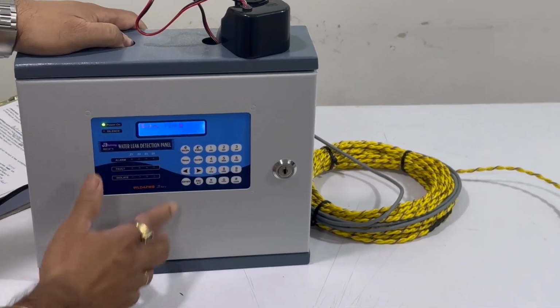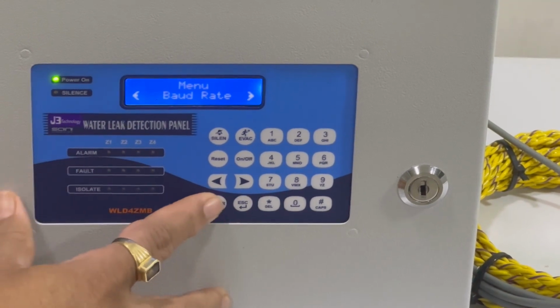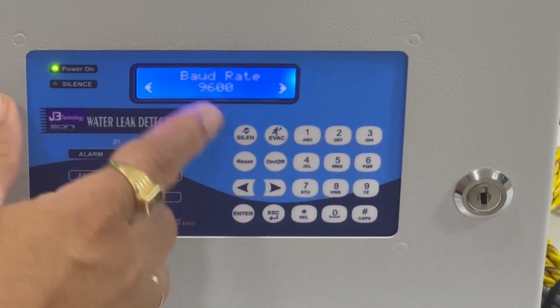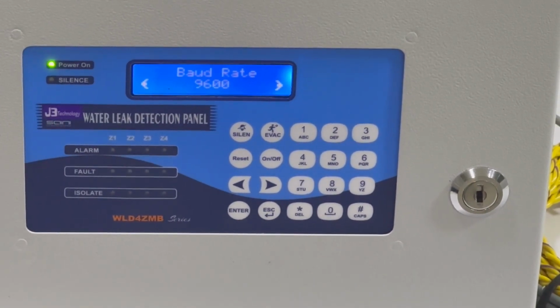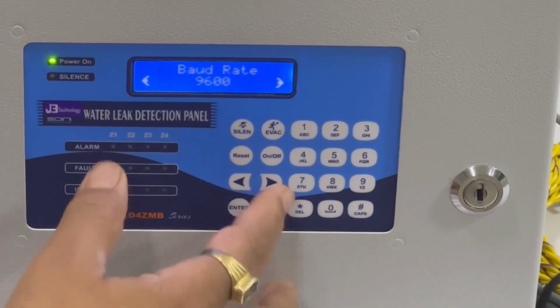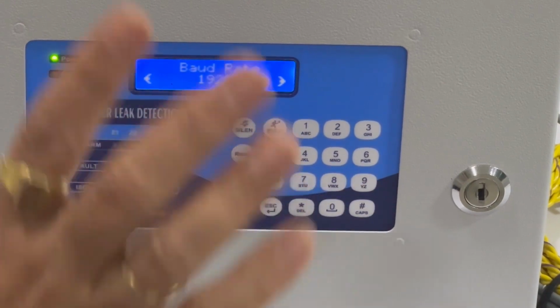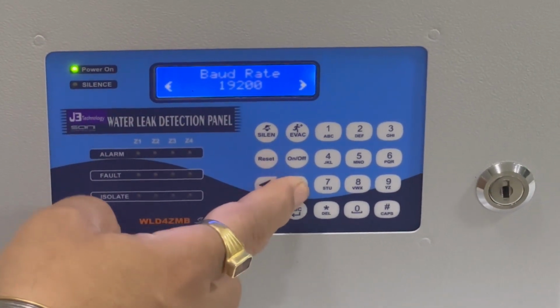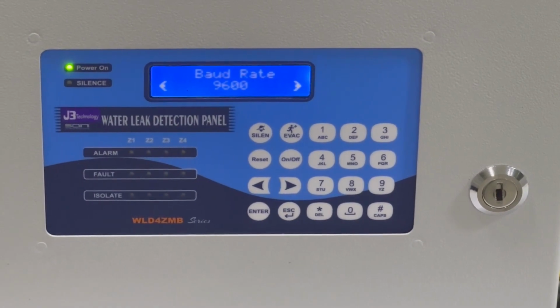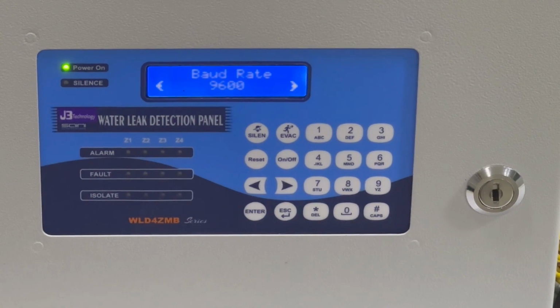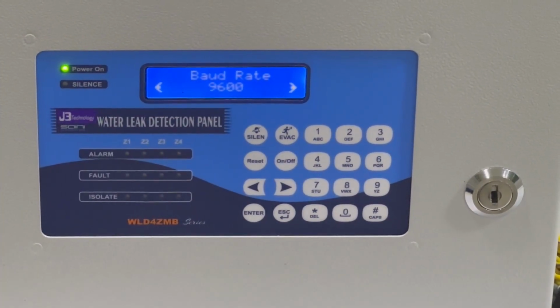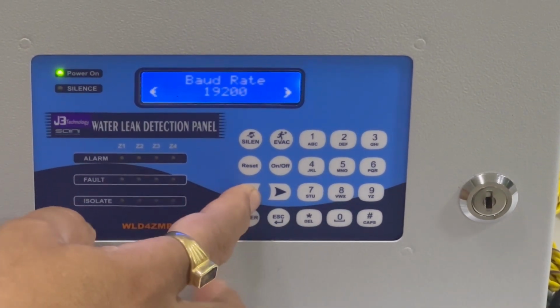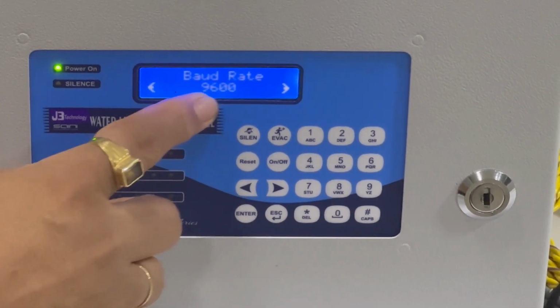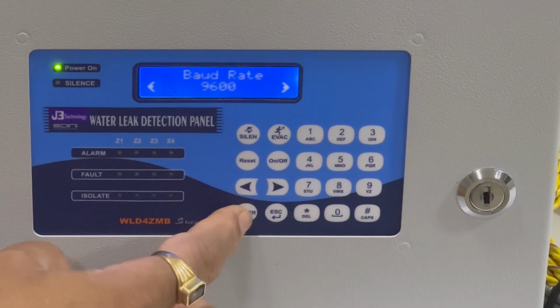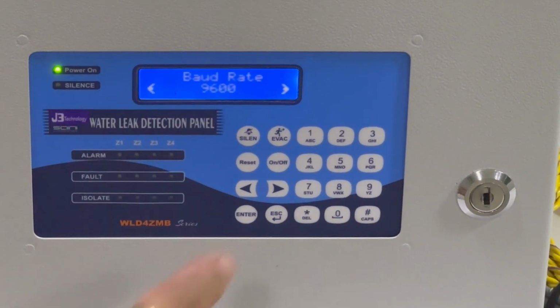Now guys, I will show you the next feature of this panel. The BAUD rate. The BAUD rate is basically used for connecting the BMS. For BMS, you just have to enter. According to your third party service, the BMS, the building management system, may ask for a BAUD rate of 9600, or might want 19200. So according to the third party service, you can select the BAUD rate, either 19200 or 9600. These are the two BAUD rates commonly used by the major players like Honeywell, Siemens, Johnson Controls. Mostly the BAUD rate used in the BMS system is 9600. You just have to select this and enter. It gets saved. That's all. This is the BAUD rate feature.